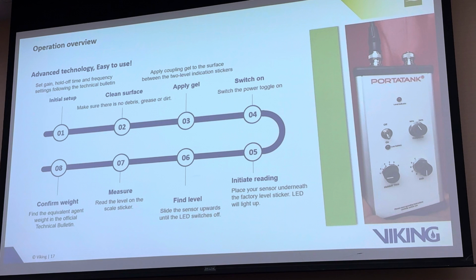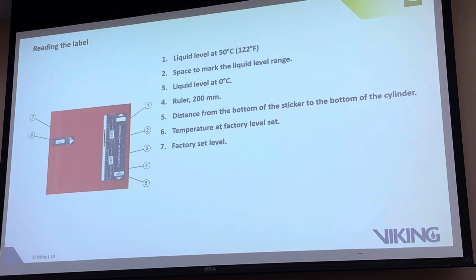You find the level, measure it with the sticker measuring tape that you have on the side, and then confirm the weight using the manual. If this is the level that I found, my cylinder is 926, my pressure is a 50 bar system, I go to the manual, read the table - I'll show shortly how - and then you know what the contents are.